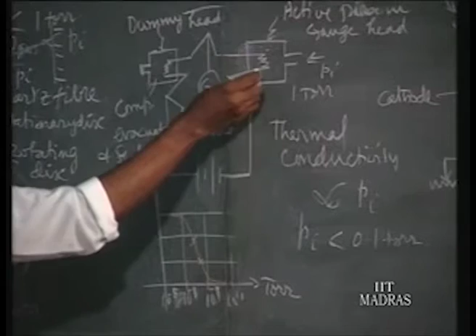It's a short range because if the vacuum falls below 10 to the power minus 3, what happens? The heat is conducted not by gas molecules but by the support. The support of the wire will carry the heat to the casing, and hence the principle is very much affected. That's why the Pirani gauge works within the limited range of 10 to the power minus 1 to 10 to the power minus 3 torr.